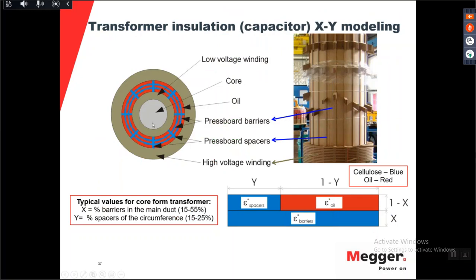And on the inside you have the low voltage winding, and in the middle you have the core. So you basically have oil and paper between the high and the low voltage side. And if you look at this, you can see, if I take one cross-sectional area here, the red one here is oil, and then I have paper and paper. So I have a paper stick or a wooden stick, and I have a wooden cylinder going all the way around here.